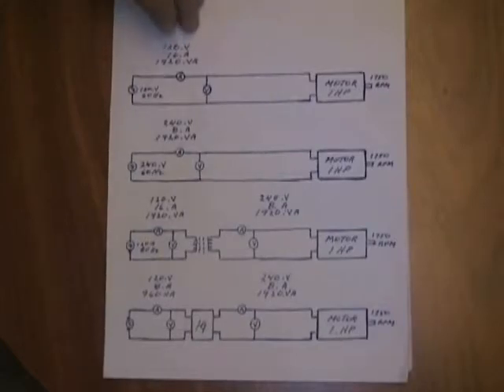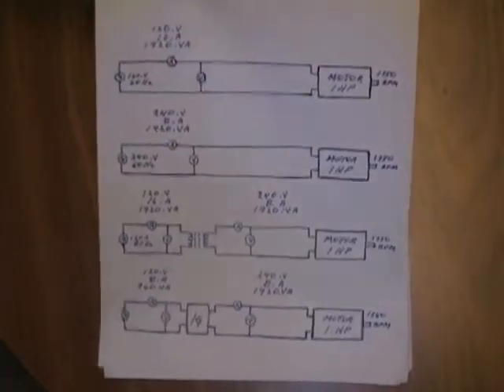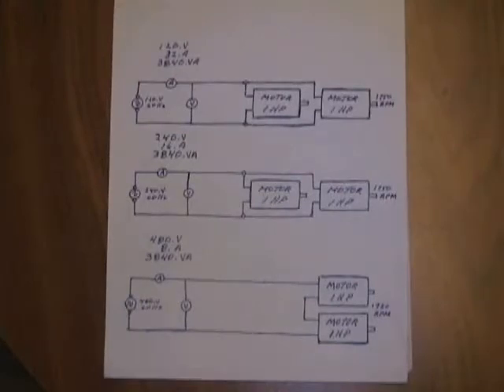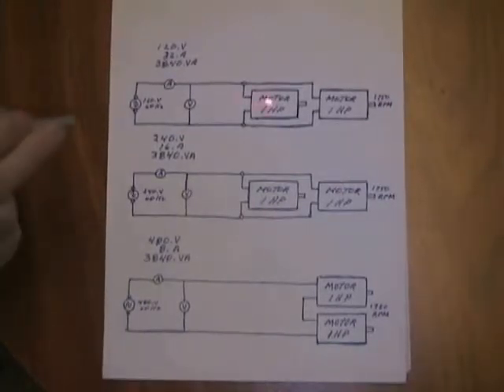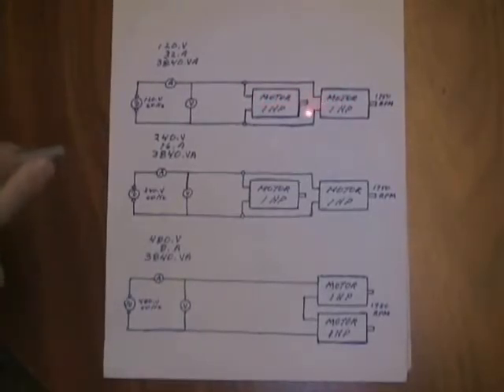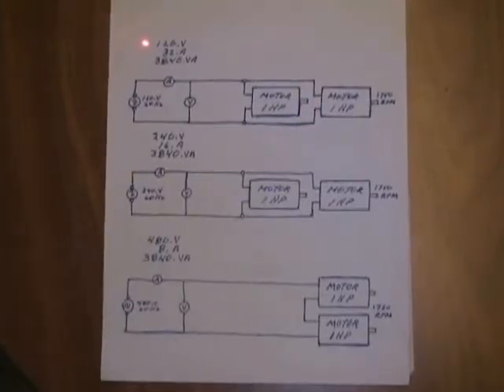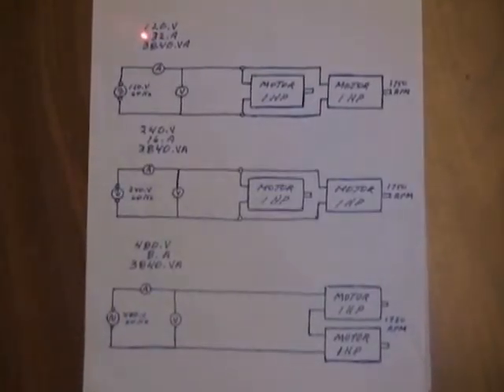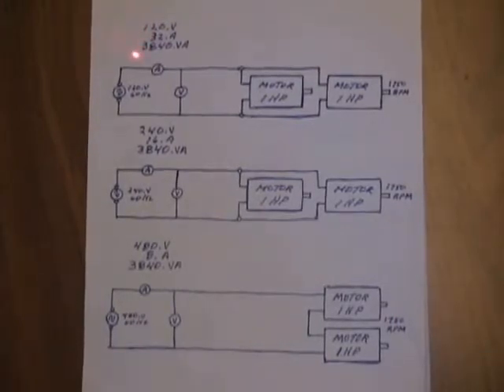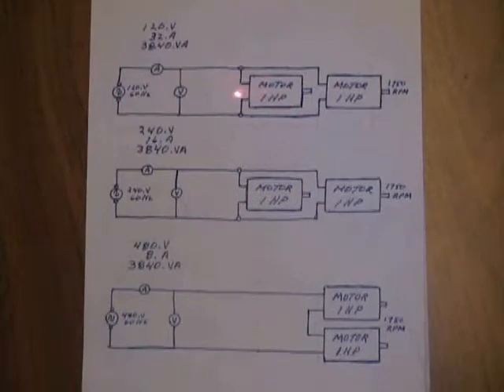Now let's go to a second drawing, second page, where we will have two motors connected in parallel here, which normally will require 120 volts, 32 amps, which is a total of 3840 volt amps, and we are going to use two similar motors of 1 horsepower each, and each will be running at 1750 RPMs.